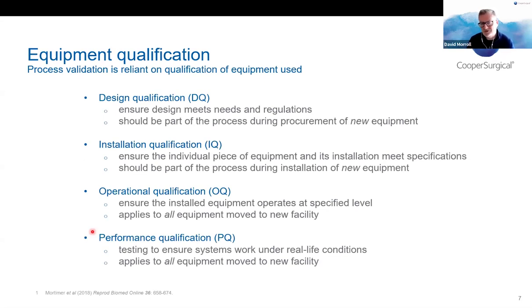Now you've probably already seen this. This is the general overview of the stages of validation or qualification of equipment. DQ, IQ, OQ, PQ, so design, installation, operational and performance. And design qualification is obviously what you're setting out right at the beginning when you are buying new equipment, what it's intended for and what sort of performance is expected. Installation, as the name suggests, is when you're putting that equipment into the lab, making sure it's installed and does what it's supposed to.